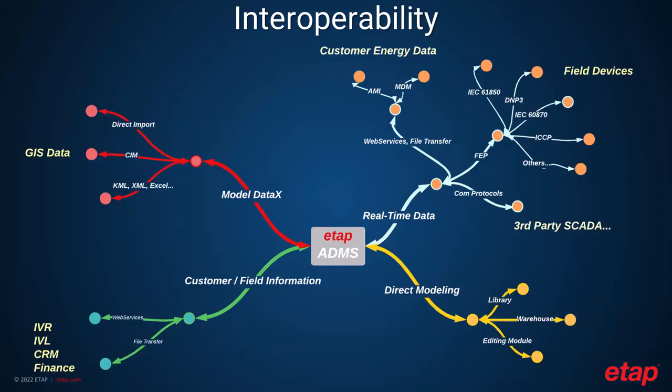Interoperability is one of the challenges that most ADMS systems face. The information centralized in the digital twin is diverse — from real-time data to technical information to enterprise management data such as CRM, billing, IVRs, and more. We have prepared the ADMS system to overcome this challenge by providing a large library of communication protocols that allows us to communicate to third-party SCADA or go directly to field devices using IEC 61850, DNP3, IEC 60870, ICCP, and many other protocols.